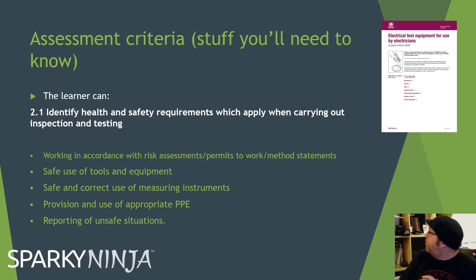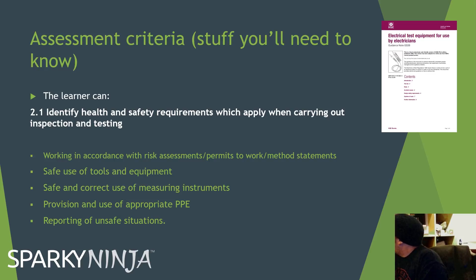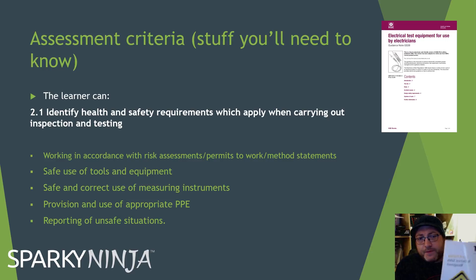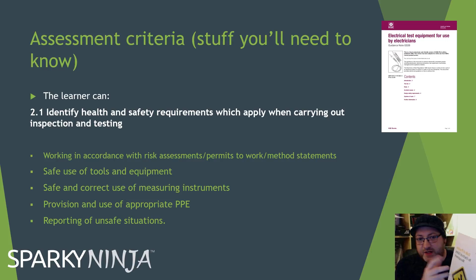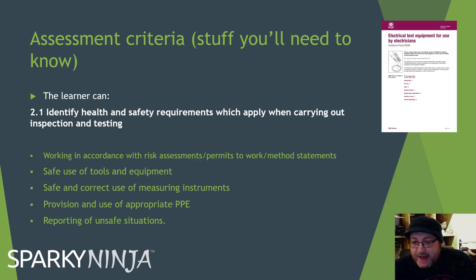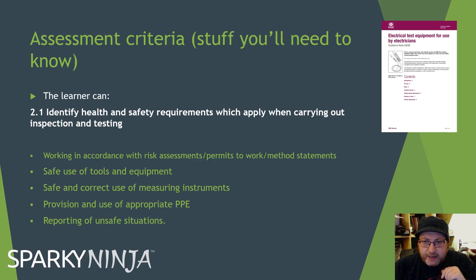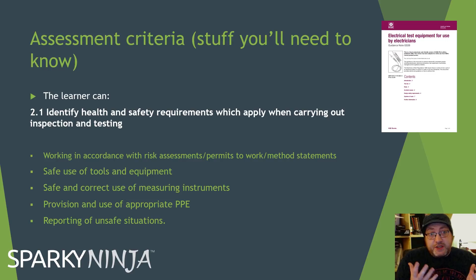If you're working on a construction site, there's PPE for the environment. If you're working in domestic, it's a less risky environment. From an electrical perspective, PPE would mainly be eye protection if there's a risk of arc flash, although you probably shouldn't be working there if there's a significant risk. Gloves maybe, but we try to recognize suitable selection of PPE. There's a good book — the Code of Practice for Electrical Safety Management, the IET code — which covers live working and the hierarchy, with PPE right at the bottom, because all inspection and testing work is live work really, unless you only do continuity measurement.